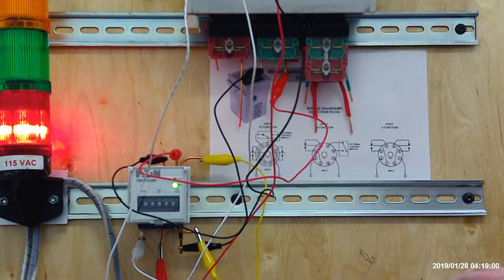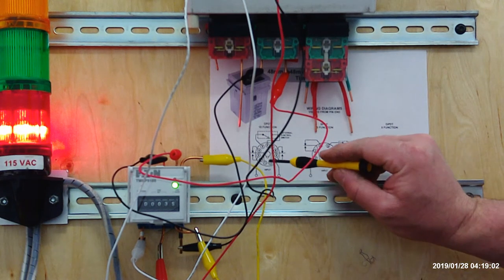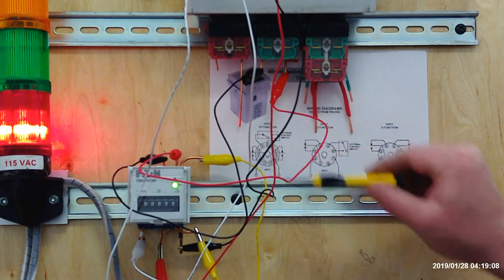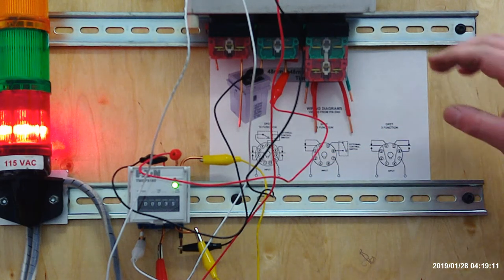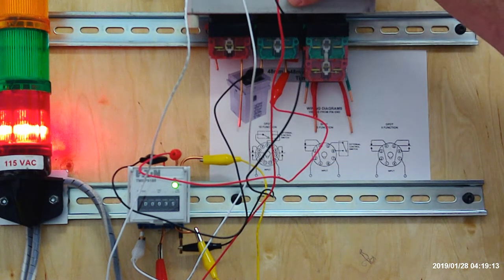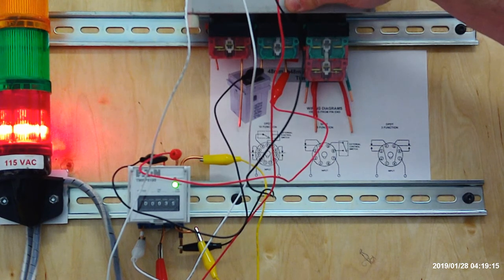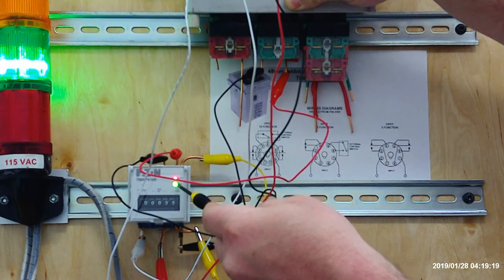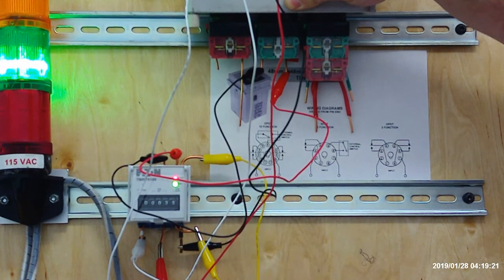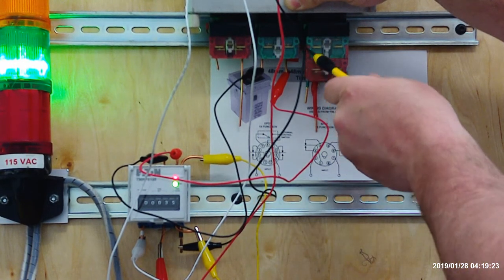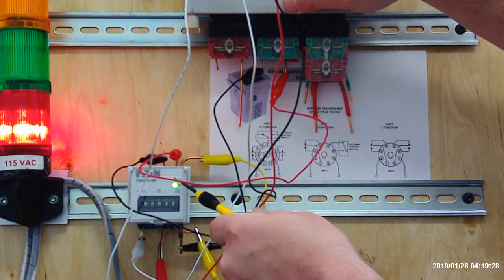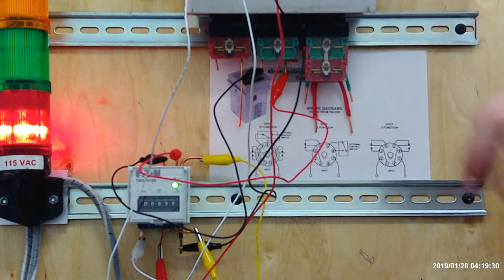All right, in its resting state the energy is flowing from the one to the four and that's where we have our red light hooked up. The green light will be when we push the three. The important part is the focus on the contacts. You'll see that once I close the contacts up here, the output is on, it's just waiting. Once I open the contacts here it starts timing, and once it times out it goes back to its resting state.